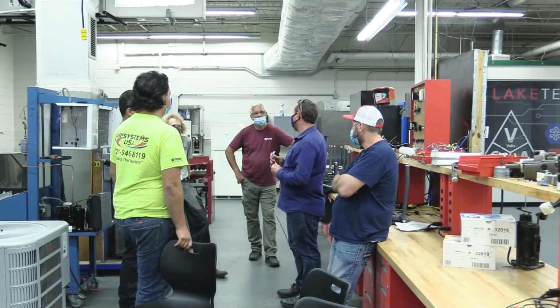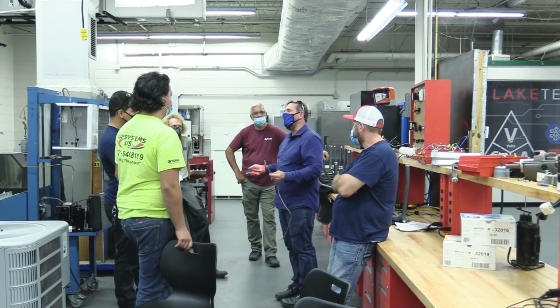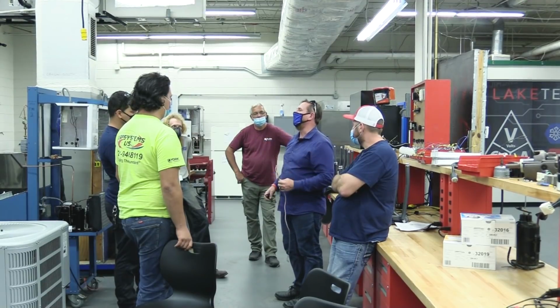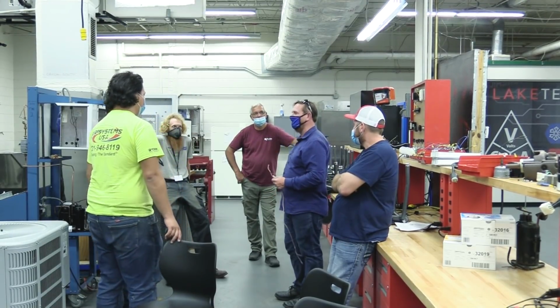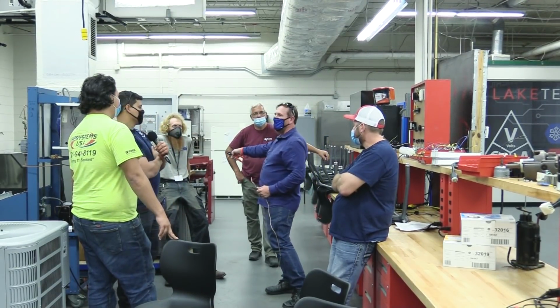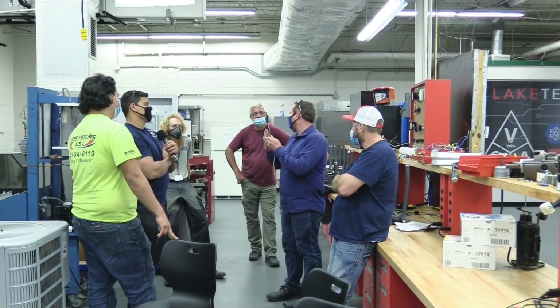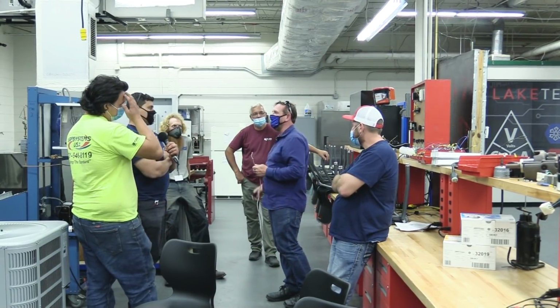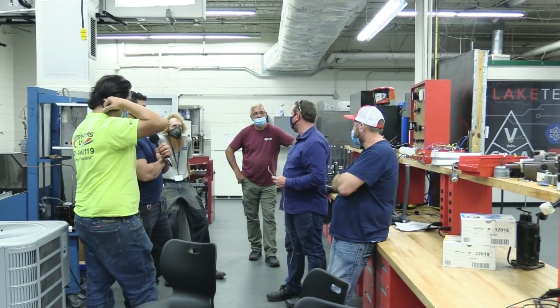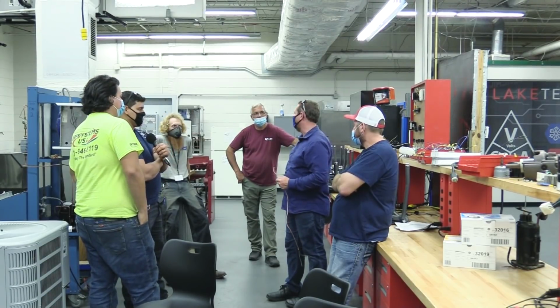You start finding common spots. Hey, I know where the shorts hang out. They like to hang out where this guy cuts the wire, that's where the shorts hang out. I'm going to go look there first. I'm going to go look in that condensing unit where carrier runs that wire right up against that suction line and it vibrates and rubs against it. I know that's a bad place to leave a short. I'm going to go check that out, see what's happening in there.